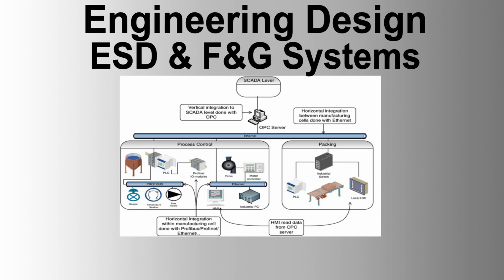4. Processor capabilities. The main processors shall have the capability to implement all control functions required to execute the logic schemes. Redundant processors shall execute the same instructions and programs, and cross-check the outputs continuously.